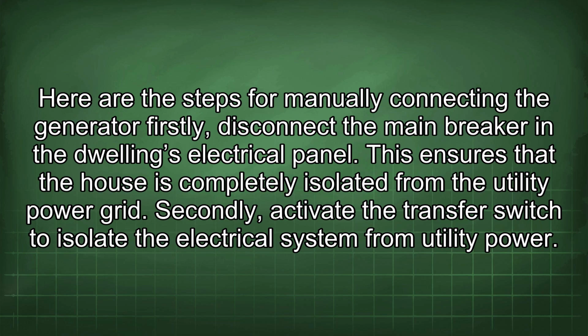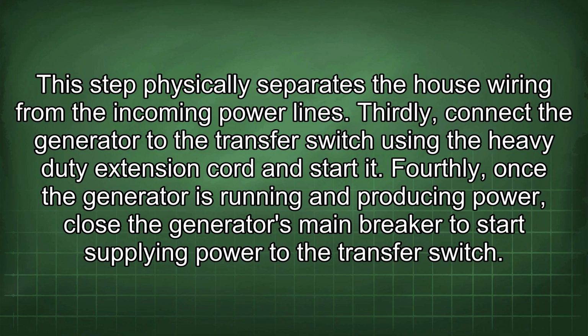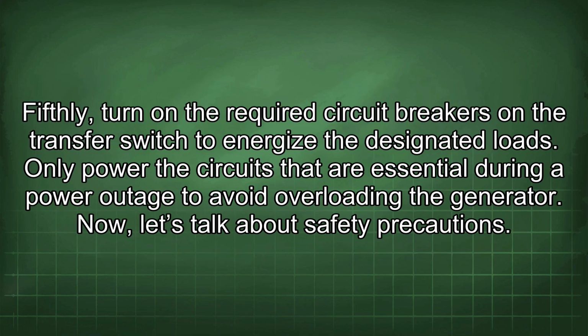Firstly, disconnect the main breaker in the dwelling's electrical panel. This ensures that the house is completely isolated from the utility power grid. Secondly, activate the transfer switch to isolate the electrical system from utility power. This step physically separates the house wiring from the incoming power lines. Thirdly, connect the generator to the transfer switch using the heavy-duty extension cord and start it. Fourthly, once the generator is running and producing power, close the generator's main breaker to start supplying power to the transfer switch. Fifthly, turn on the required circuit breakers on the transfer switch to energize the designated loads. Only power the circuits that are essential during a power outage to avoid overloading the generator.